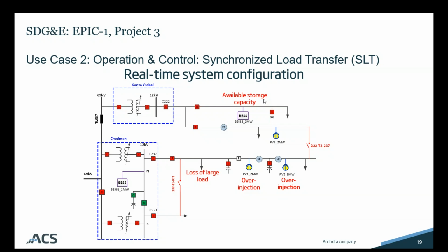So with that, what the system can do is what we call a synchronized load transfer across this normally open tie. You would need to make sure that you have a sync check in place, and you would want to be monitoring the voltages and controlling the voltages across that normally open tie before you close in and create that loop feed. But once you can do that and do a real-time system reconfiguration, you can now divert that power injection and still utilize it without curtailing it and utilize that available storage capacity.